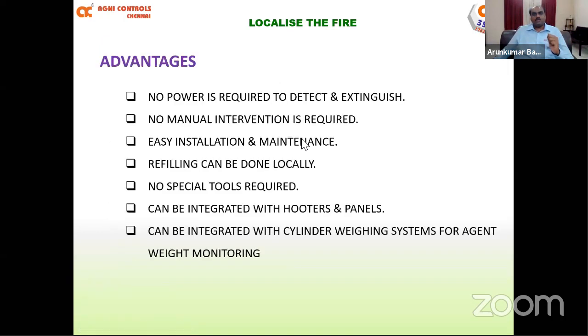Now the advantages. We saw the limitations of a manual extinguisher, so what we are trying to do is automate it. One of the main things required when automating a manual extinguisher is that we don't need electrical power, because once you have electrical power, you need battery backup, and you must ensure the battery and electricity are always on for the system to operate. This entire system operates on pneumatics, so it doesn't require any electrical power, making it very easy to convert manual extinguishing methods to automatic ones.